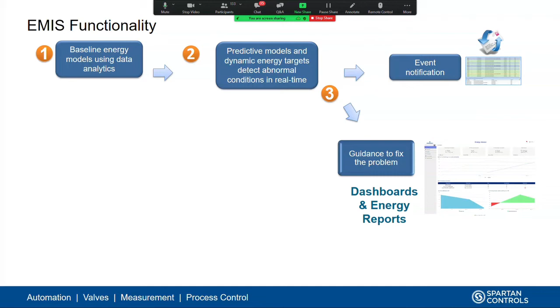The analytics will point us and tell us right away in real time, as you see here on the lower left-hand side, this is what your problem is. You are having a problem, you are getting high energy consumption, and that high energy consumption is being caused by this root cause. And as we demonstrated, that root cause can also be incorporating the information from our online condition monitoring systems. So we've taken the information from the online condition monitoring system, and now we've incorporated it into the analytics in our EMIS to make our EMIS much more powerful.